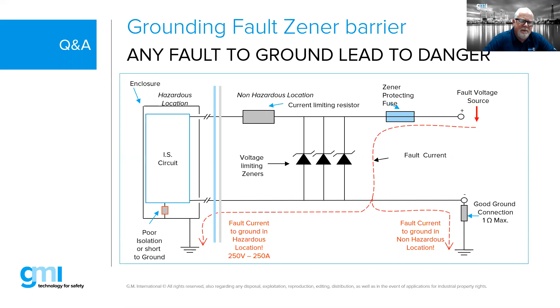Can I install an IS barrier in the field, in a remote area? Yes, and I think we had this question too about purging and pressurizing. You could certainly take barriers and put them inside flame-proof enclosures to install them into a zone 1 area. But remember, many barriers or associated apparatus are already suitable for zone 2, so they can go into other protection concept enclosures for zone 2. Always look at the protection concept of the barrier itself and where it can be applied. But sometimes the cable has to be kept very short, so you might have to install those barriers fairly close to the field devices. Purging and pressurizing, or flame-proof/explosion-proof here in the United States, is also an option.